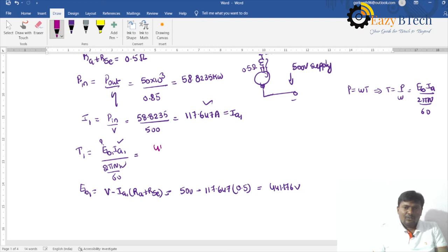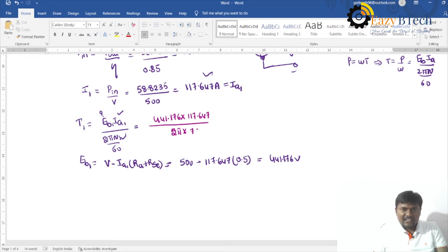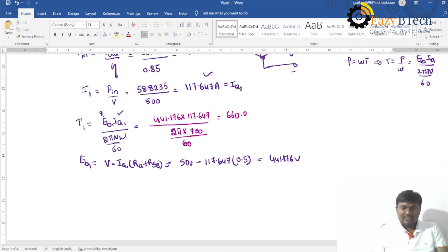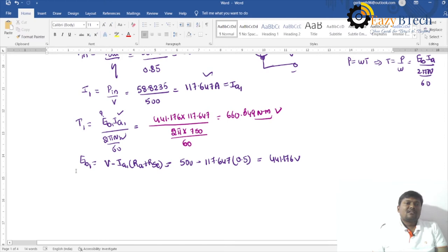Substituting: T1 = 441.176 × 117.647 divided by (2π × 750/60) = 660.849 Newton meters. So the back EMF is found using that formula, then substituted into the torque equation to get T1 = 660.849 Nm.